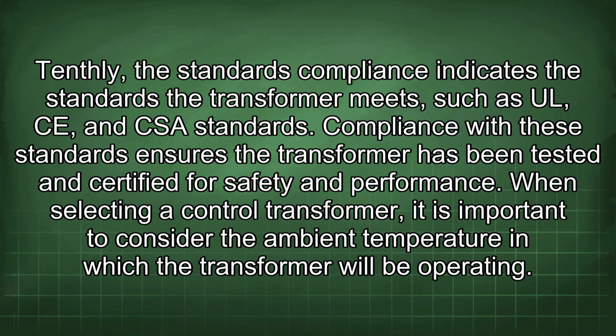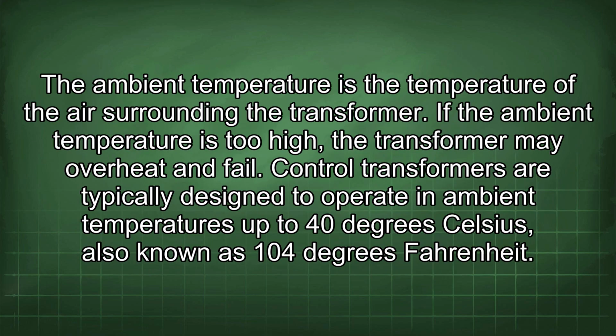Tenthly, the standards compliance indicates the standards the transformer meets, such as UL, CE, and CSA standards. Compliance with these standards ensures the transformer has been tested and certified for safety and performance. When selecting a control transformer, it is important to consider the ambient temperature in which the transformer will be operating. The ambient temperature is the temperature of the air surrounding the transformer.